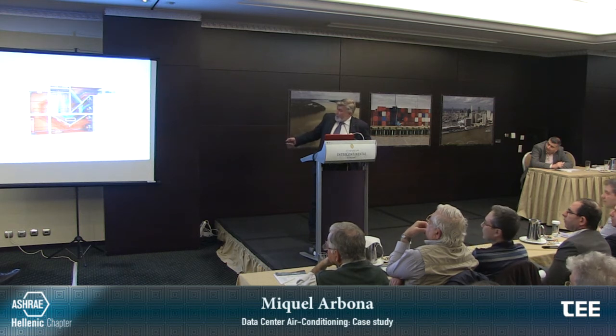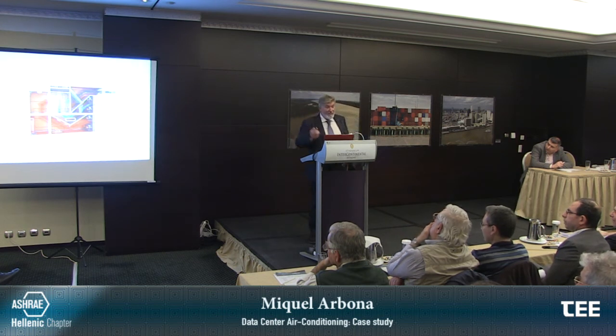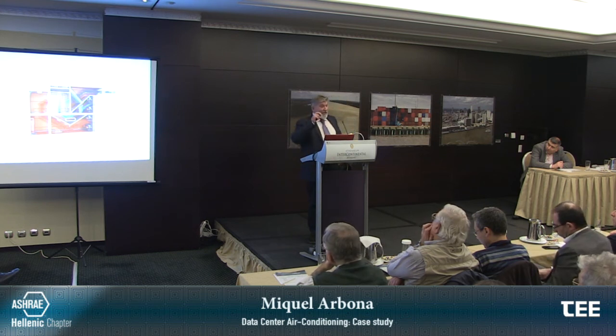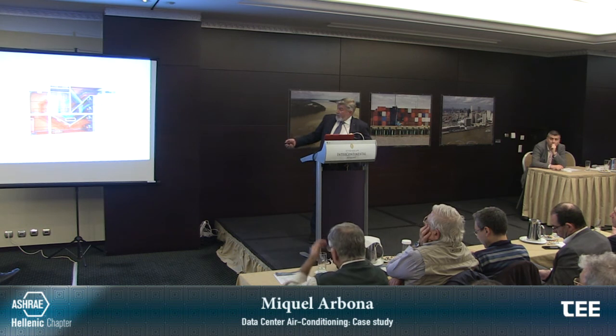You see here there are more fans, and there are more fans because, of course, the data center managers want security. So they say, okay, you say you only need 50% of the compressors, but I want to have 100% of compressors just in case you don't have water. So you have to be able to produce 100% of power without water, and this is why we have more compressors and fans there. But really, the outside fans are working very low.